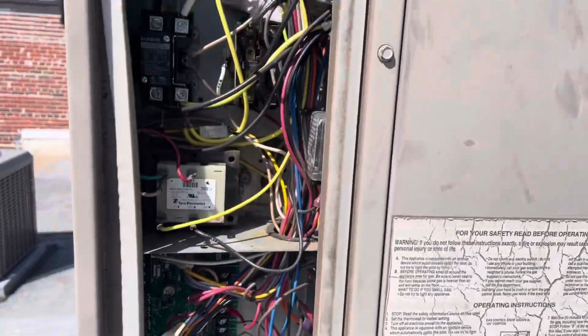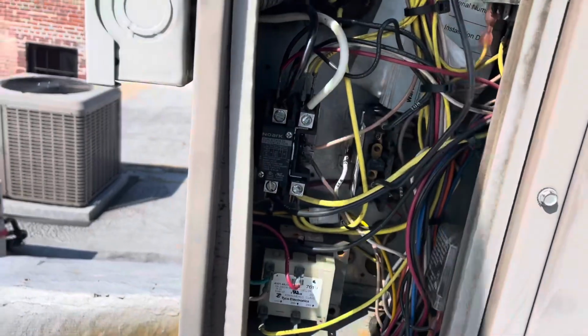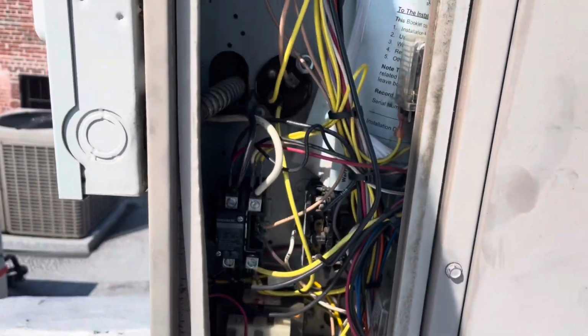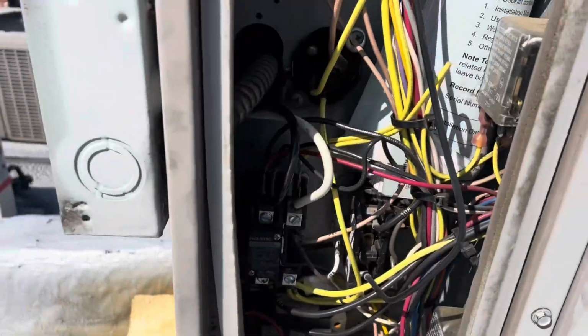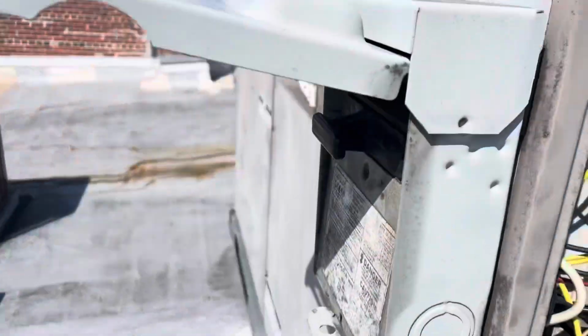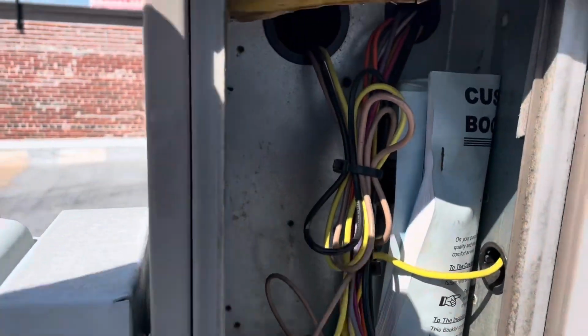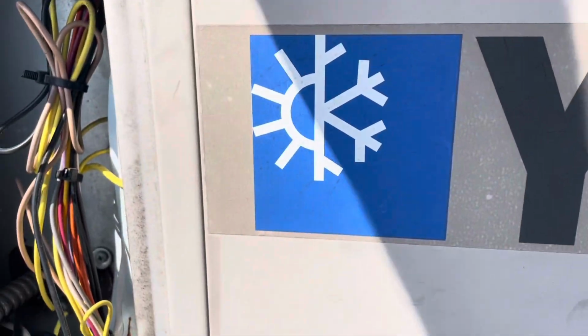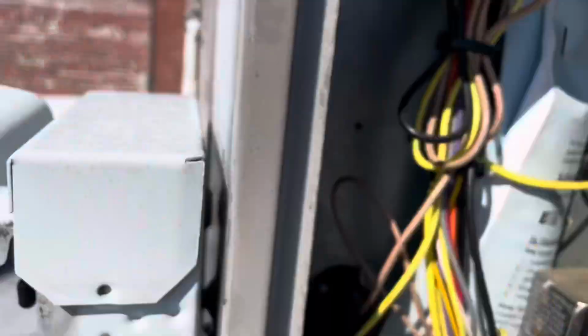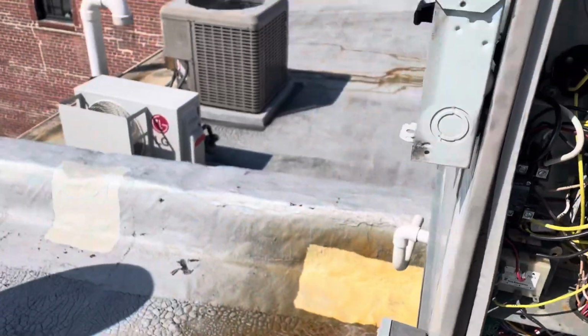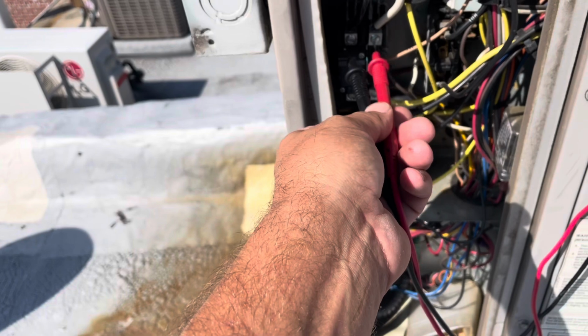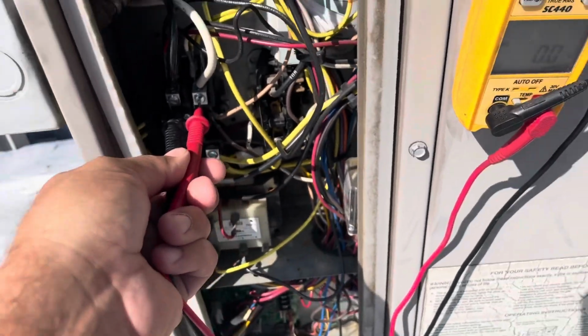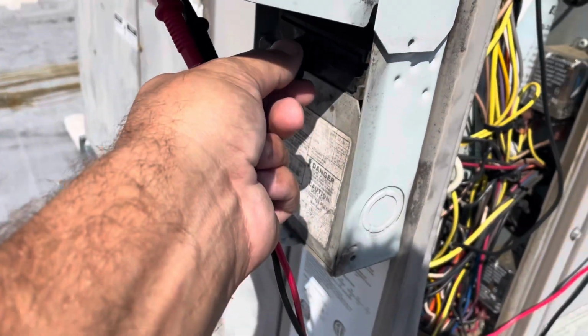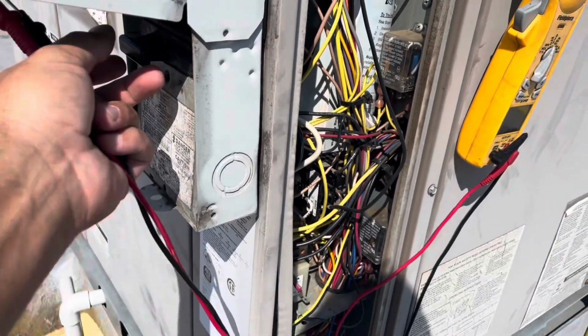First observation is the low voltage circuit breaker is not tripped. So we're going to test high voltage, then low voltage. I have no high voltage, and as soon as I lifted that disconnect again, I heard a crackle. So I've got a feeling we have a bad disconnect here, or at bare minimum a bad fuse pull. Let me check right now, see if it made a connection. Yeah, see, it's not there now. Look at that.